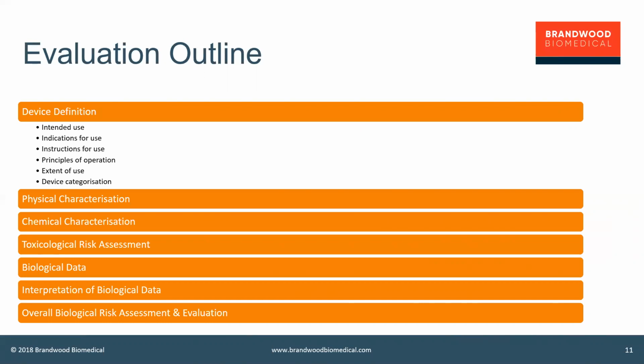Chemical characterization may not be the same as physical characterization at all. It may be a very extensive and complicated process. But chemical characterization is to facilitate the TRA. And in fact, although they're listed here as two separate items, they actually overlap and interweave with one another. So the toxicological risk assessment is actually done in and through the chemical characterization process rather than necessarily after it in sequence. Then there should be the biological data, where it exists.